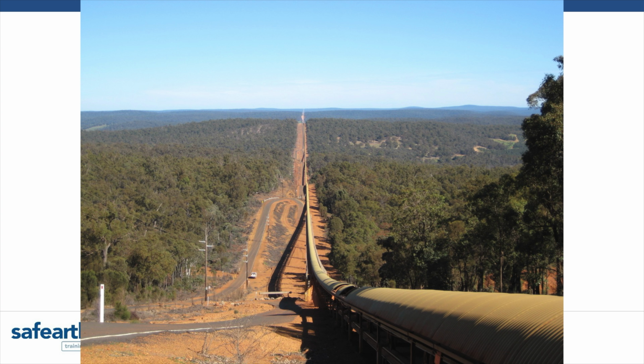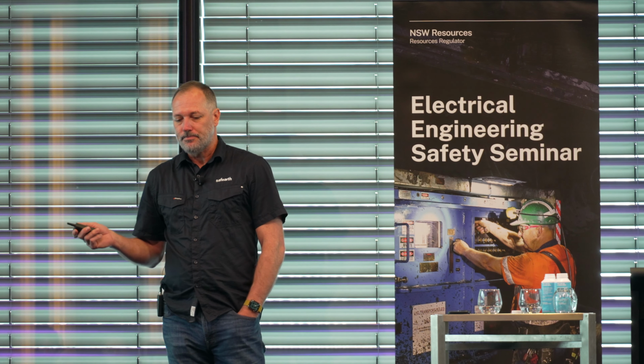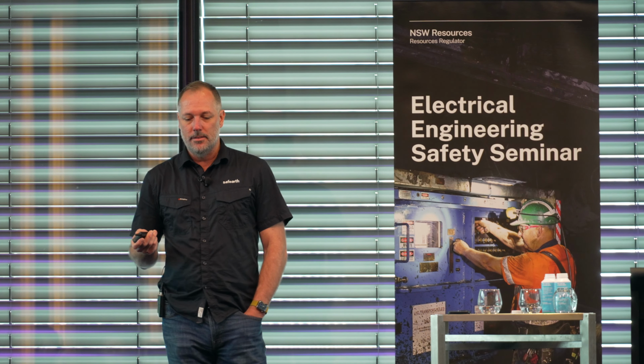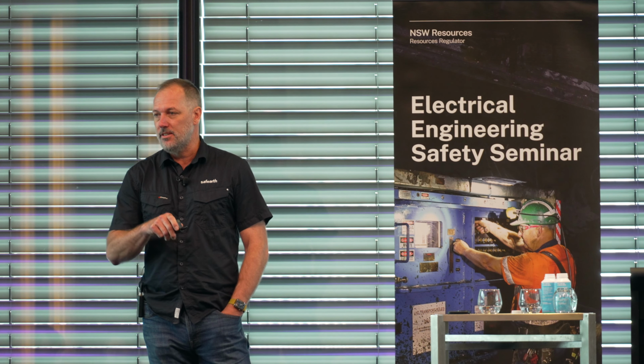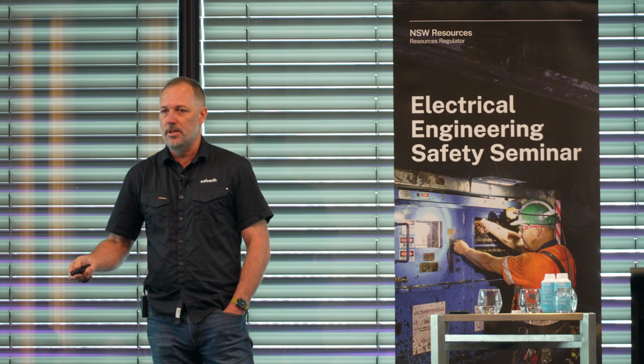Up in the Bowen Basin many years ago, there was a conveyor next to a 66 kV line. I believe a crow landed at the very end of the line on a wet day, and the crow died, and every e-stop along the entire conveyor just exploded. No one got hurt, but you can see how powerful that interaction can be. The low frequency induction phenomenon between a faulted phase conductor and something else can be pretty dramatic.